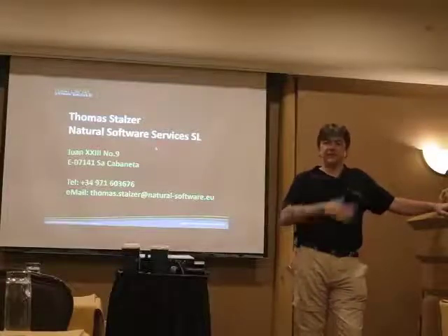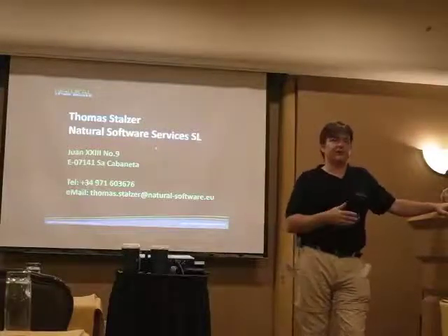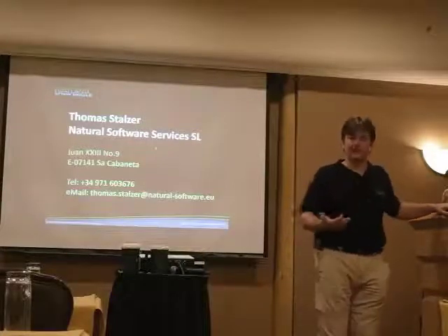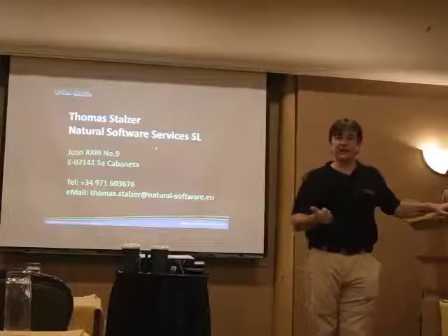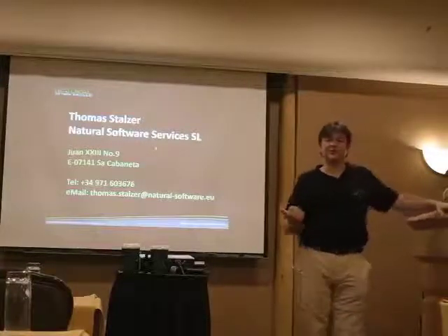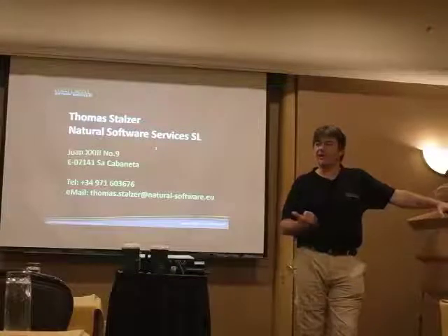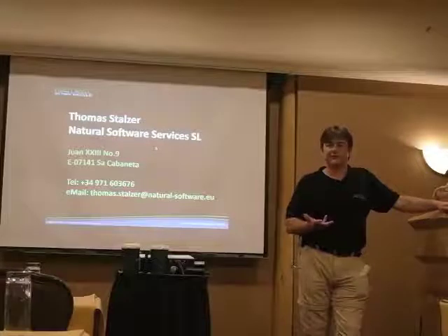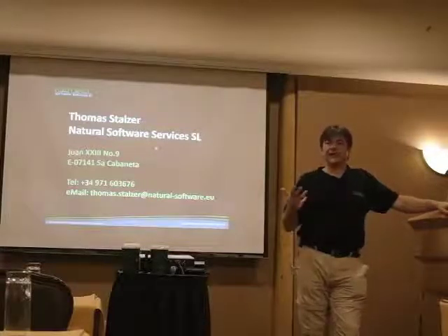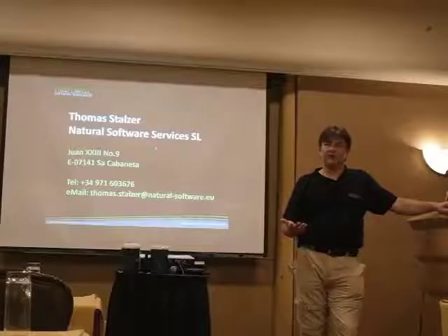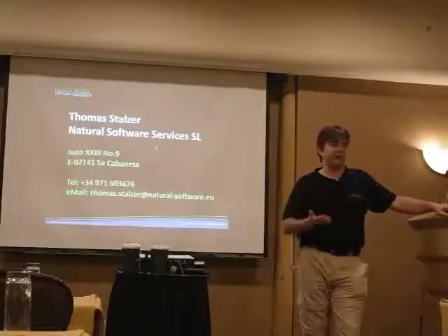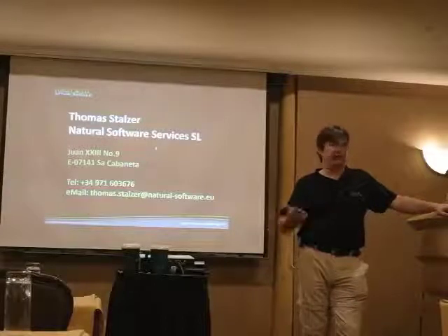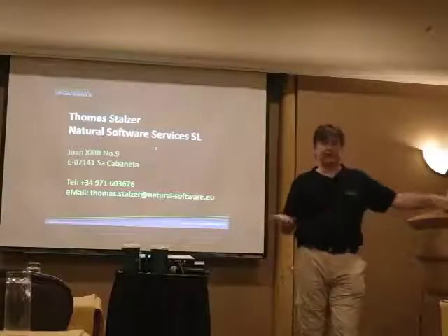The system is controlled by user ID password. So per default, we have 3 levels, well actually 4 levels of security, which is public. That's the only thing you're allowed to do when you're a member of public, is see the login screen. Then we have guests, users, and administrators. And for each level, you can define which objects you're allowed to manipulate and which objects you're allowed to see. You can define your own security levels, and you can manage the system any way you want.